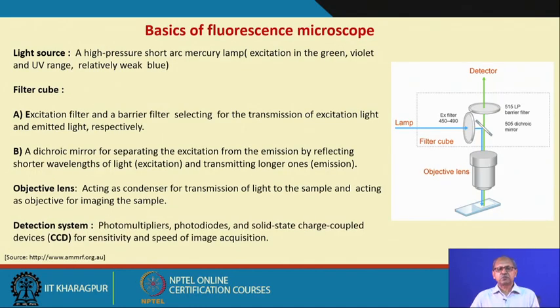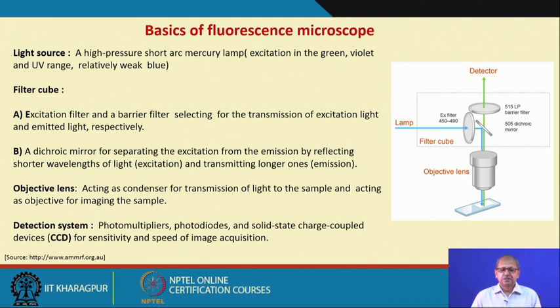What type of microscopy shall we use for the microfluidic system? First, we discuss wide-field fluorescence microscopy and its components. The light source is a high-pressure short-arc mercury lamp, which gives excitation in green, violet, and UV range with relatively weak blue. Then there is the filter cube, which consists of an excitation filter, a dichroic mirror, and a barrier filter.